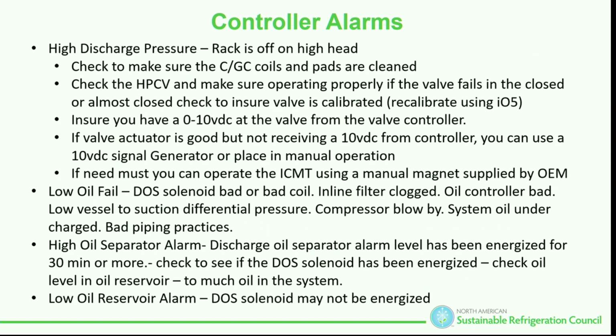Yeah, and so we're going to see some of this. High discharge pressure leads to a lot of places. How many people agree with that? Let me back up. Has anything I said yet been new to you? Or are these common sense refrigeration things? Refrigeration, yeah. You apprentice, you first year and second year. These are things that we carry over, doesn't matter what time. We've got a half hour, so I get to be preaching. You've got to follow the drawings, you've got to make sure you understand. Don't start jumping things out because you don't know what that solenoid does, or what that oil line is.